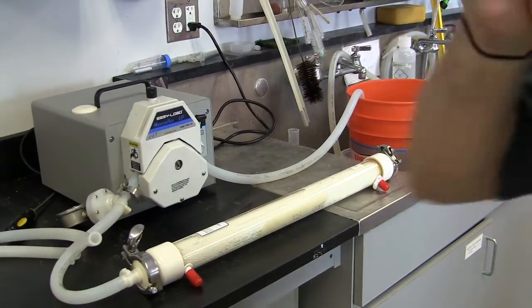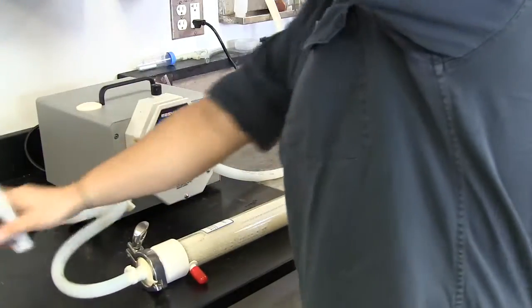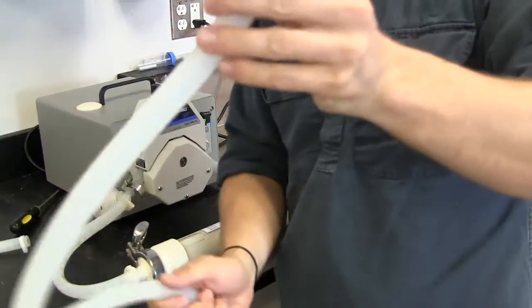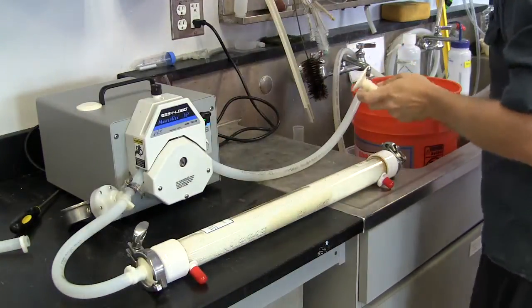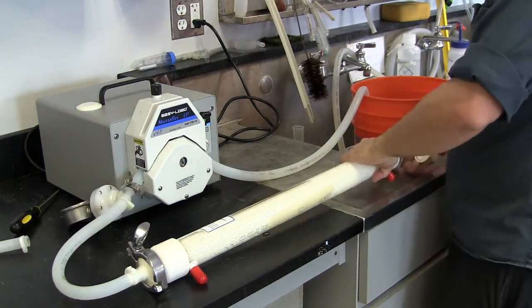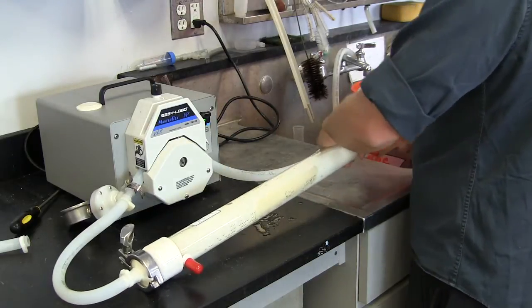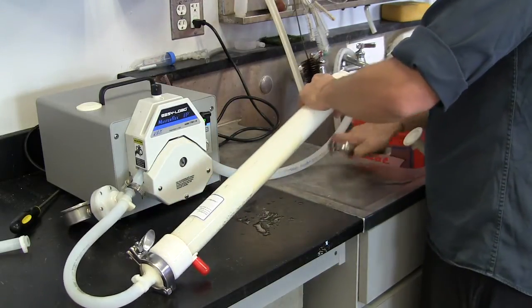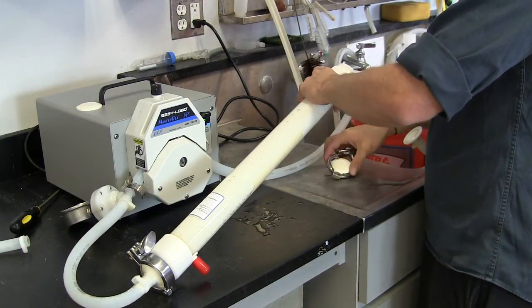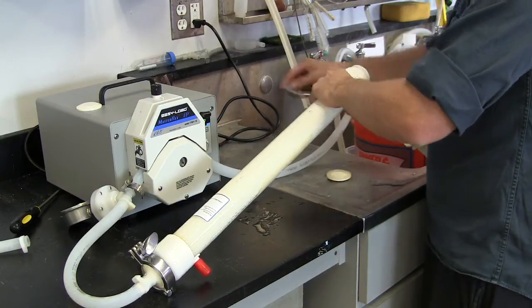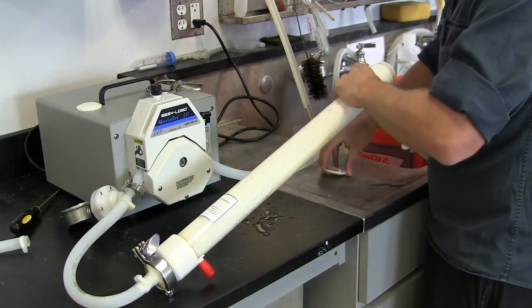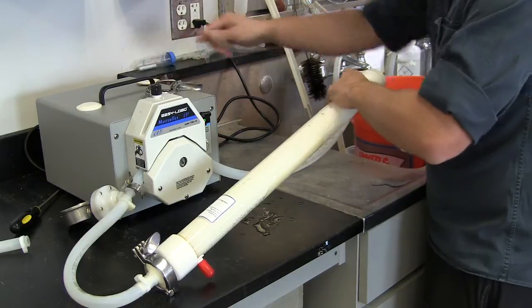Okay, now what I'm going to do is attach the other piece of tubing that is just the return line that takes liquid back into my sample or into a sink. I always do this next to a sink because you're going to want to drain either your sample as you're concentrating it into the sink, or what you're cleaning into the sink, so you're always going to end up getting rid of something down the sink.